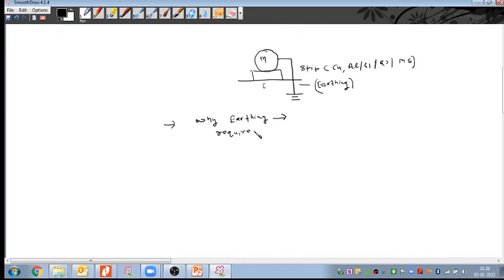Does anyone have any opinion about this? Why is earthing required? This is Arva, sir. Yeah. Fault current is going through earthing, sir. If earthing is not there, fault current is not possible to ground. Correct. Fault current is not possible to ground. Then what will happen? The current surrounds the equipment. It will give a shock if and when you touch. Okay. Then what is the next problem?